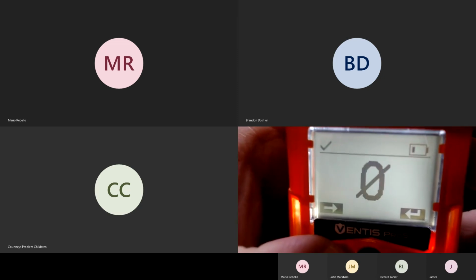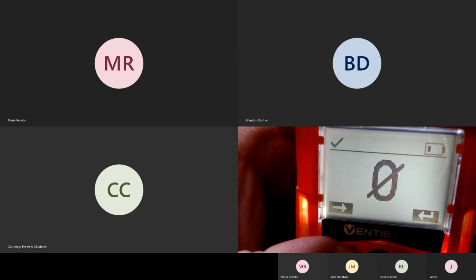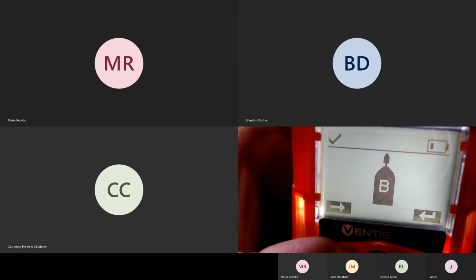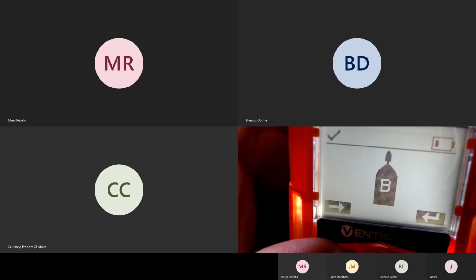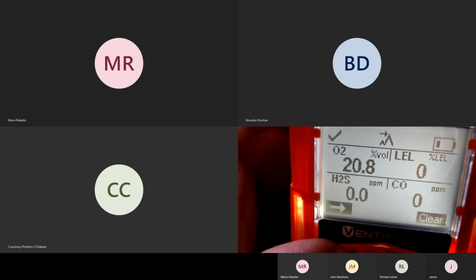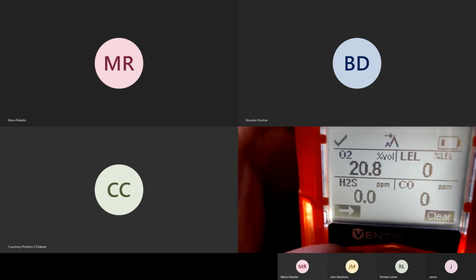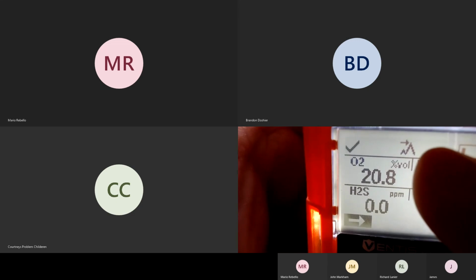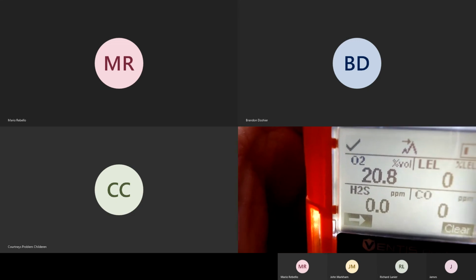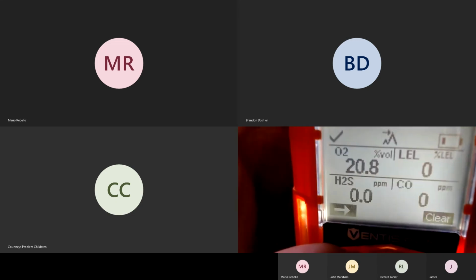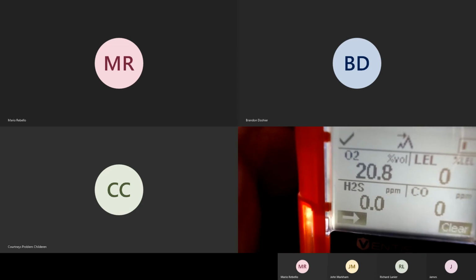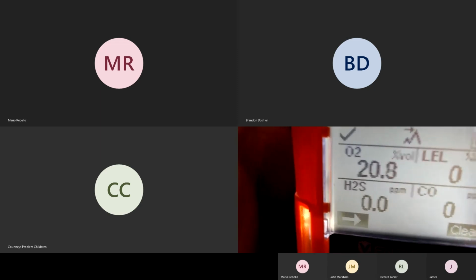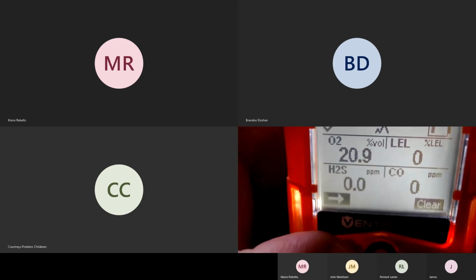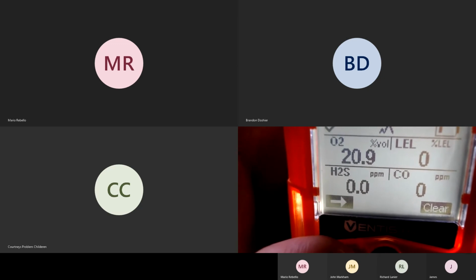All right, so there's my zeroing again. As I click through again, there's my bump if I need to do a manual bump test. Then here's my peaks, okay? So up here at the top, you'll see the little mountains with the arrow pointing towards the peak of the mountain. This shows me the highest reading of all gases I've seen except for oxygen. It shows me the lowest. To clear it, I just press the enter button where it says clear, and it will clear it out, okay?